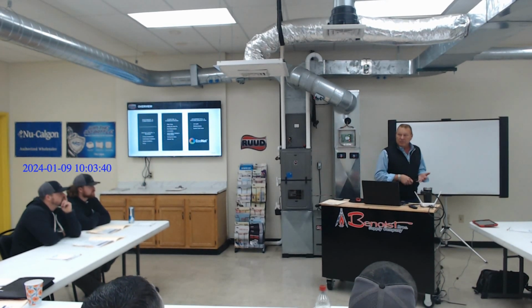Two-stage outdoor units run at about 69%, and I think some of them are maybe now 65% of full capacity on single stage. I only have two. Well, my heat pumps are all two-stage, 14 SEER. Then you get 15, 16, and 18 SEER, which is variable, okay? I have to know what my smallest zone will handle. So I don't have a calculator.